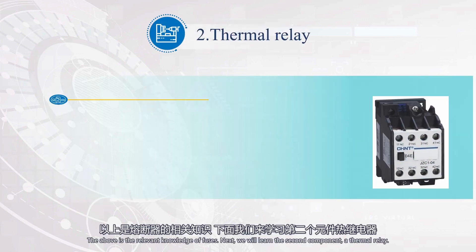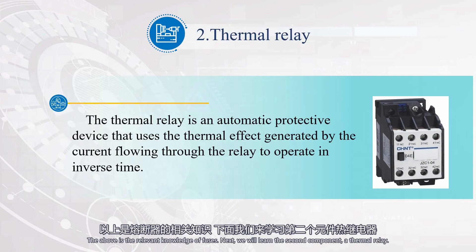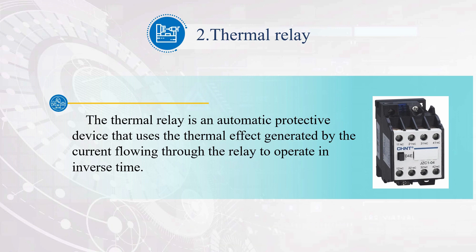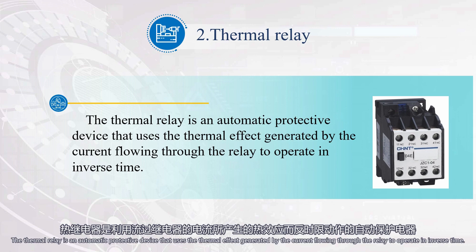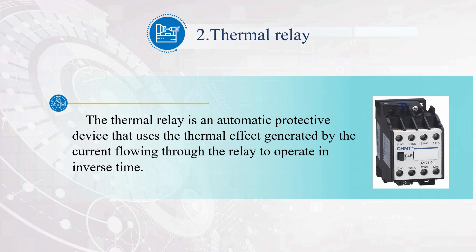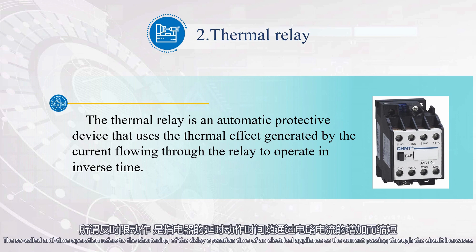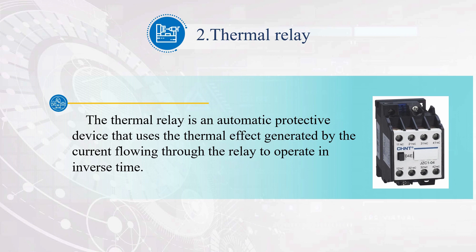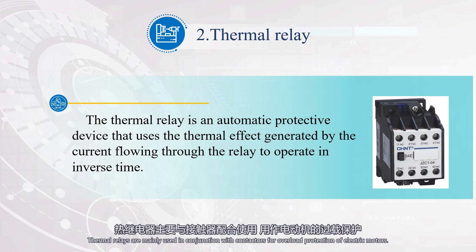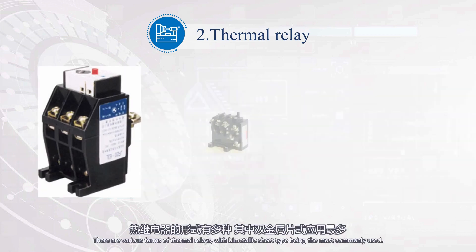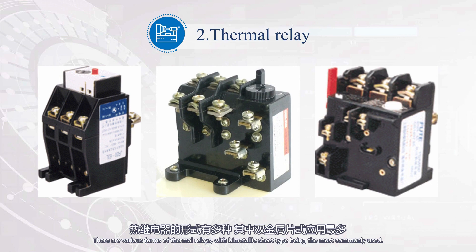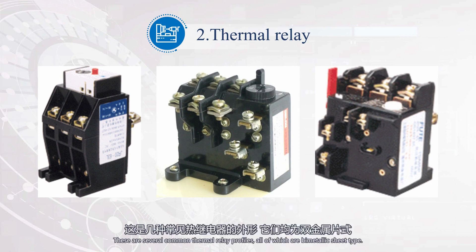Next, we will learn the second component: a thermal relay. The thermal relay is an automatic protective device that uses the thermal effect generated by the current flowing through the relay to operate in inverse time. The so-called inverse-time operation refers to the shortening of the delay operation time as the current passing through the circuit increases. Thermal relays are mainly used in conjunction with contactors for overload protection of electric motors. The bimetallic sheet type is the most commonly used form.